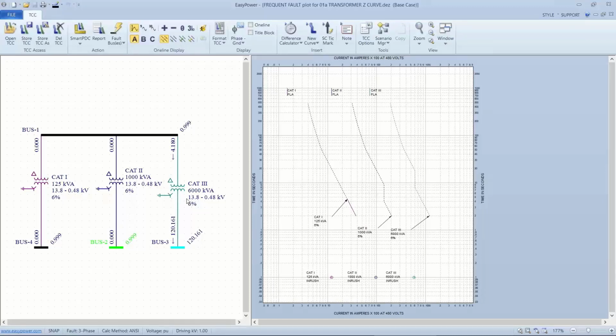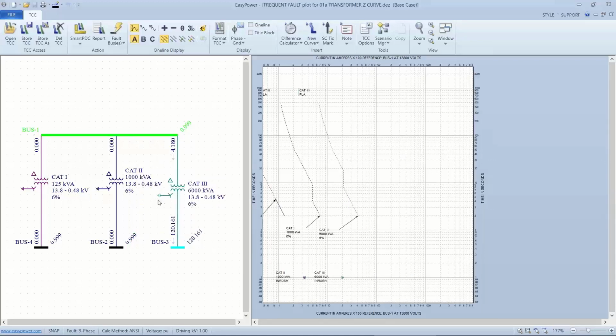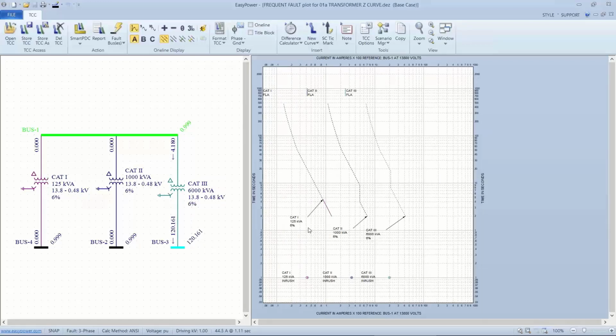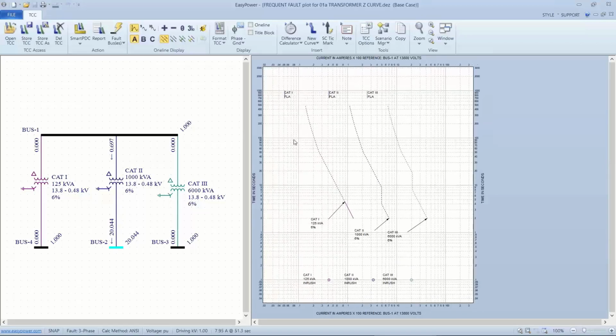If we wanted to plot them with reference to 13.8, the tool allows me to change my reference point, and it skews all of that current to the left. And now we're looking at equivalent current in the 13.8 range. So if we were setting primary protection for these devices, this would be the current that we're expecting to measure, 697 amps in the 13.8 range. And that's all being illustrated here in the range that we're showing for 13.8.